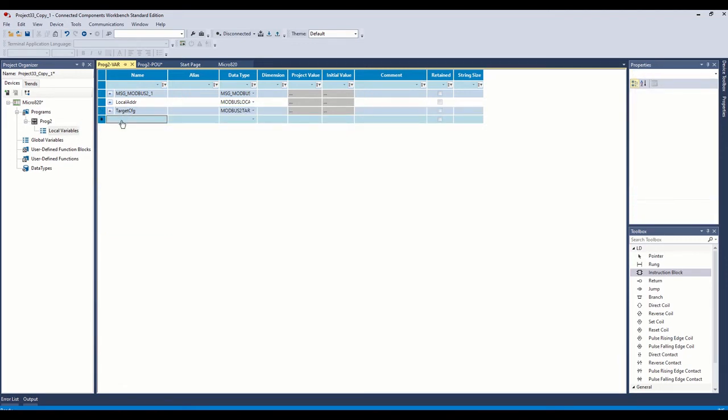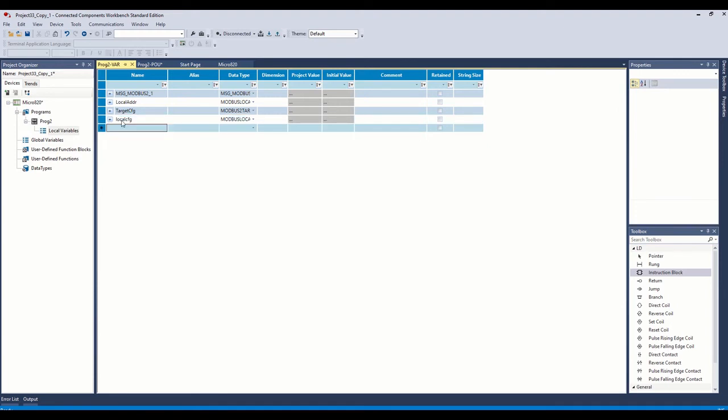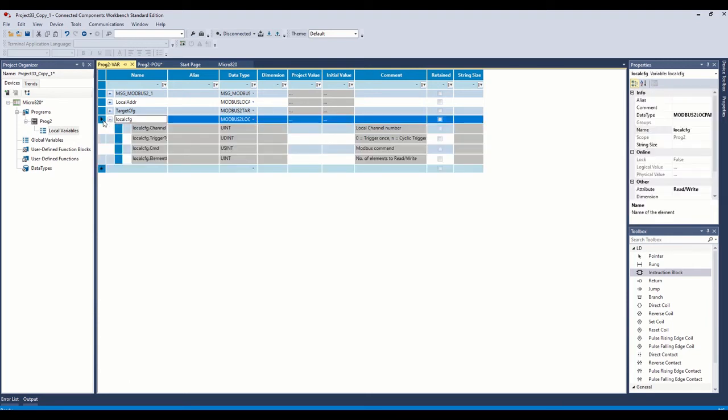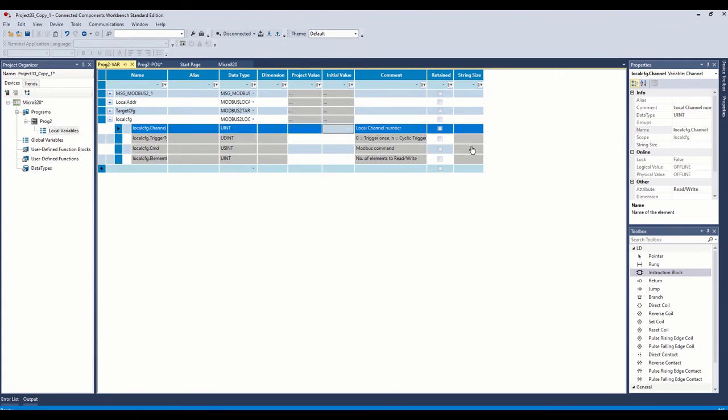The next one we need is our local config. That's Modbus 2 local parameter. And then if we expand that, this is our local information. What port number are we going to use? In the manual, you can find this on the knowledge base or in the Micro 800 programming manual, which is very easy to find. But it'll tell you that the channel number for the Ethernet port is four.